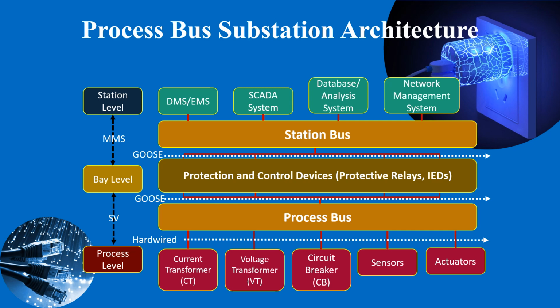This figure illustrates a typical substation architecture for an Australian substation, but there are still power utilities that are not willing to migrate to IEC 61850. Maybe because they are not comfortable with the new technology, or they need to train their personnel about IEC 61850, or they don't like to upgrade because their substation is still working fine.